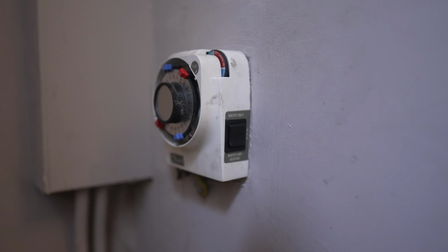We've got the boiler hung, the flue, the condensate, and all the pipes going into the boiler. What's next? Wiring. Wiring takes up quite a lot of time with any sort of job. With back boilers especially, you've got the old thermostats downstairs, most likely on the chimney breast or fireplace. This needs removing, all the wires need linking up accordingly, and you've got to find which wire has the live going through it so you can put a spur upstairs to connect to the new boiler.